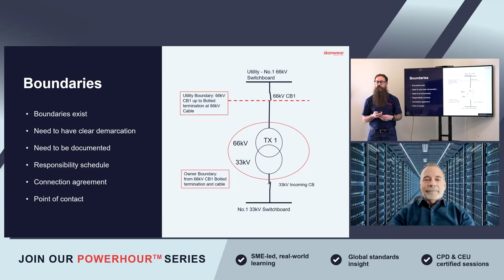Multiple boundaries. So here's an example of a renewable site, a wind farm. Again, this is just an example because I know there are multiple boundary owners there. In this example we've got a utility connection, 66 kV, up to the bolted termination. I know that up to that bolted connection on the cable, everything downstream of that belongs to the owner, and that is encompassed within their electrical safety program, and their electrical safety rules are in place on that network.